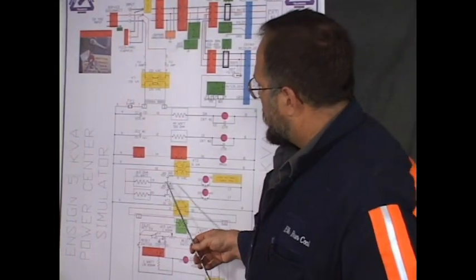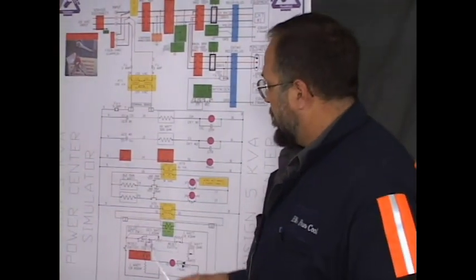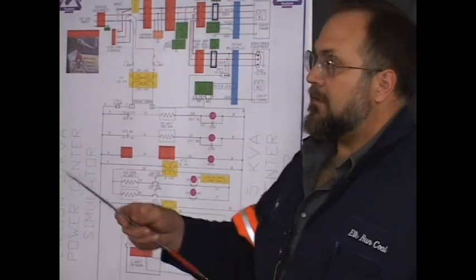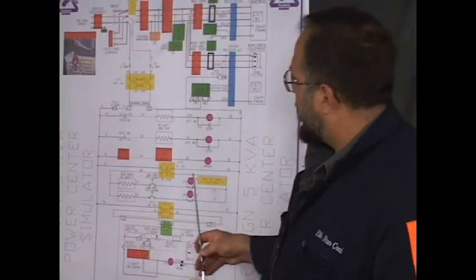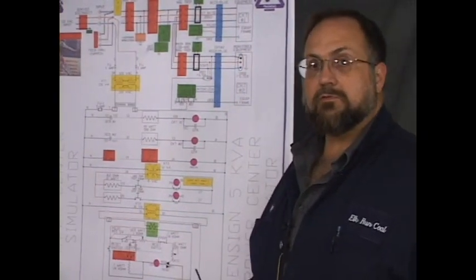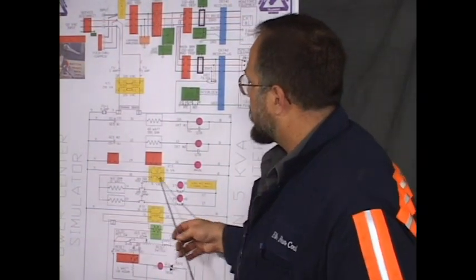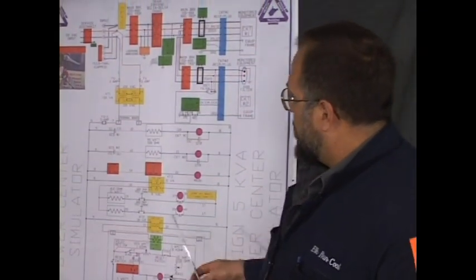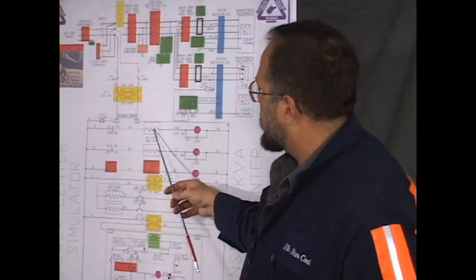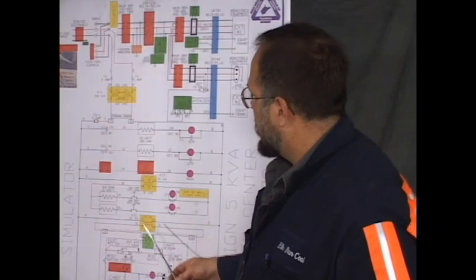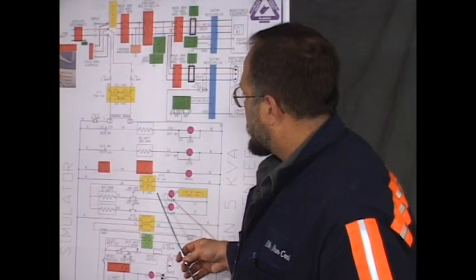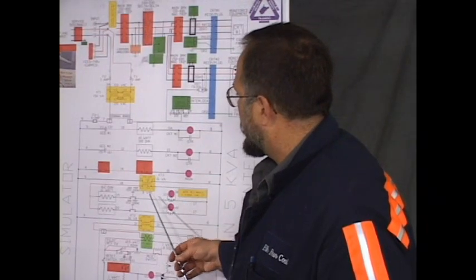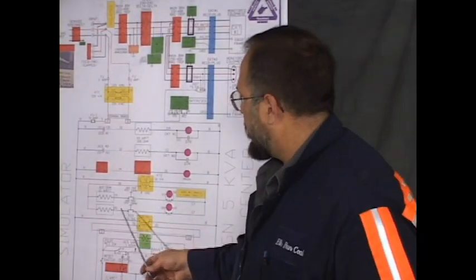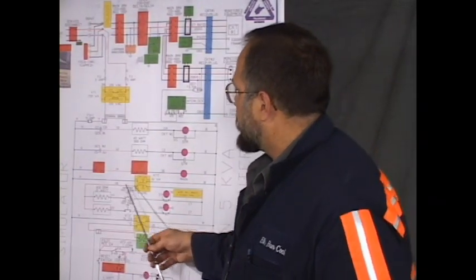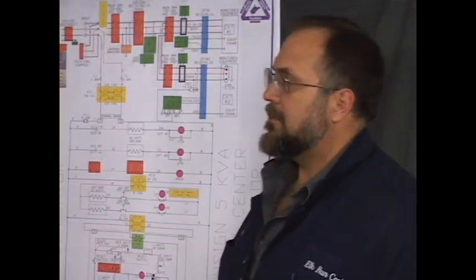This switch is drawn as normally open, and indeed it is normally open, but an ohm meter is a bidirectional device. You can't direct it to just read this switch unless you isolate the switch from the circuit. So when we attach a probe from one side to the other, we're not only going to read the switch, but we're going to read the remainder of the circuit as well. And the circuit has an 8.2 ohm resistor that's used for the same thing this one is, to stop it from being a short circuit when you close it, and a small transformer, a 16 VA KT3. It's a 120 volt to 8 volt step down transformer to drive the circuit. So I should read approximately 9 ohms resistance if this switch is good. Let's see if it's good.